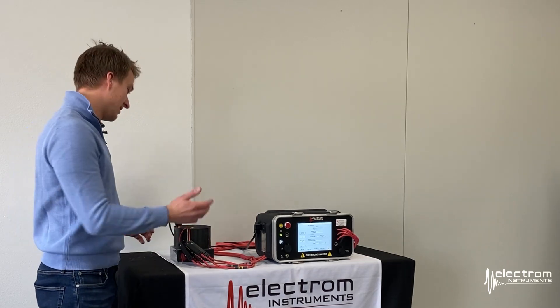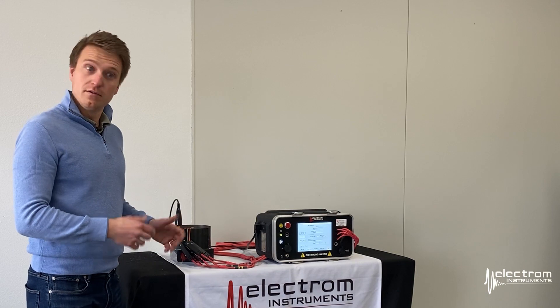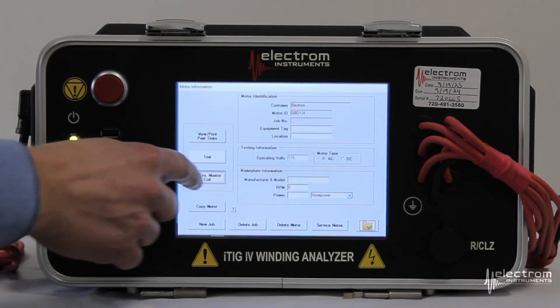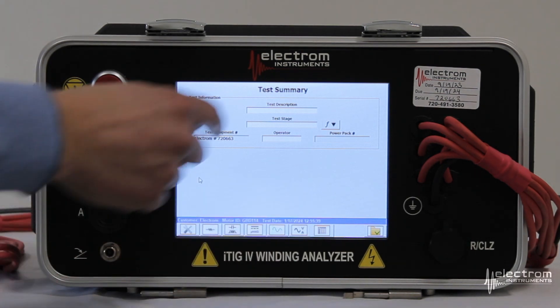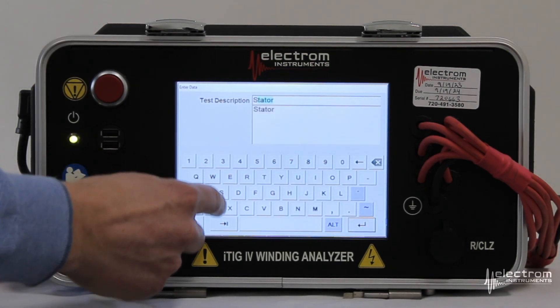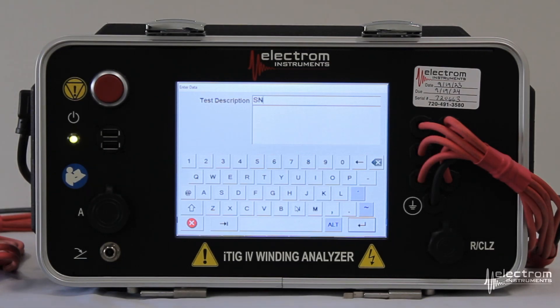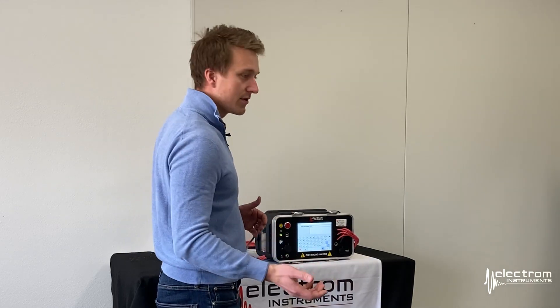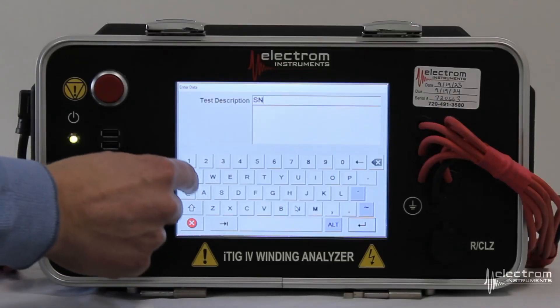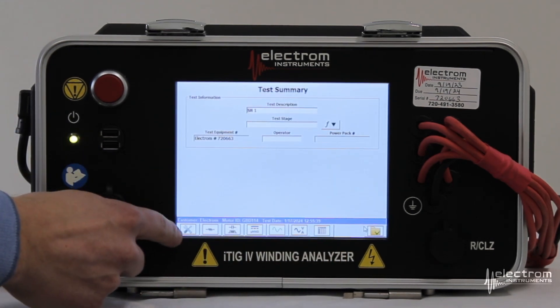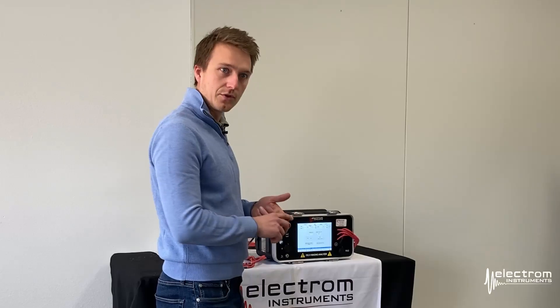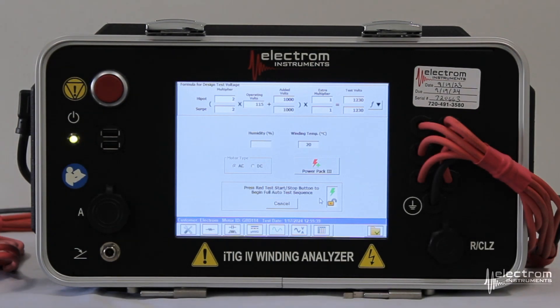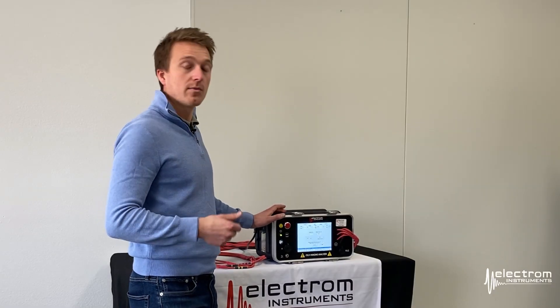Let's assume the next motor comes off the line. You make your connections to serial number one, for example, and you want to test it against the original master. Back at the tester, we now select 'Test Versus Master Coil.' We're back to the test summary screen, and in the test description field I would enter the serial number of this specific motor. For all subsequent tests, this is how you identify which motor you're actually testing. Back on the setup screen, everything we defined — test voltages, measurements, tests, and pass/fail criteria — is already saved, so there's no setup required. Just click Start Full Auto Test.